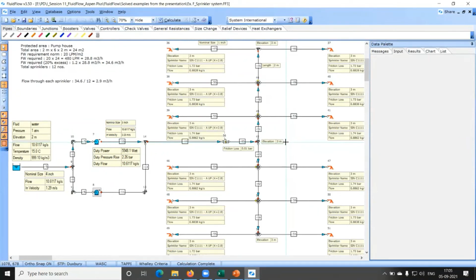We did the entire Qatar Gas fire water network simulation, and they had a lot of pipe failure issues with their GRP pipe. We modeled it and suggested remedies, to go for a surge accumulator or surge vessel. Once they implement that in the next shutdown, their frequent pipe breakage will go away.